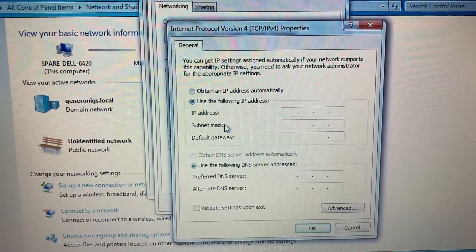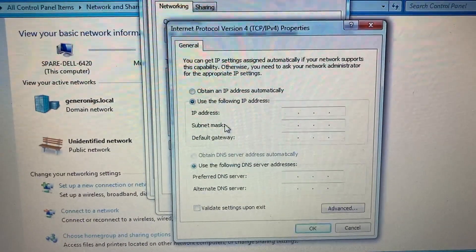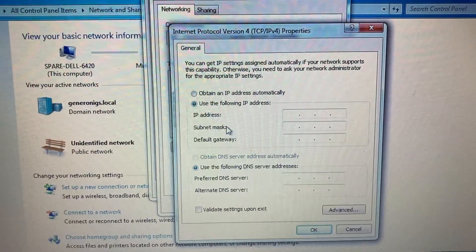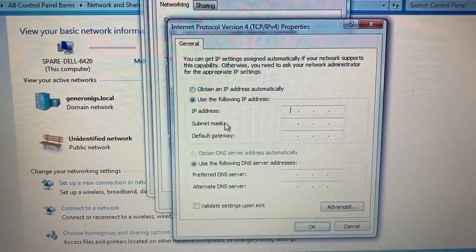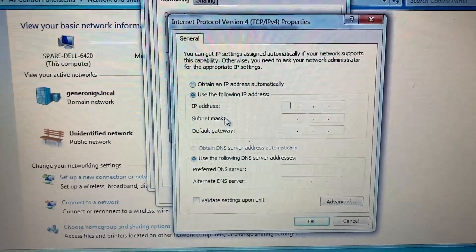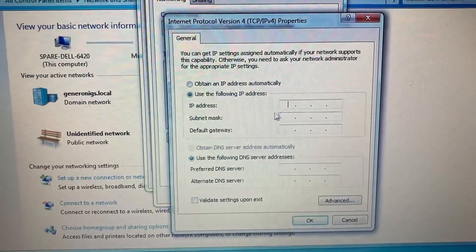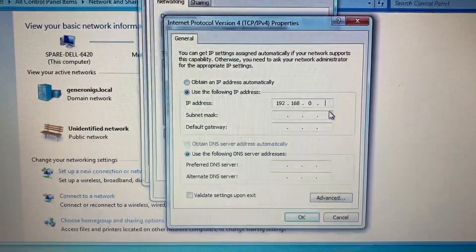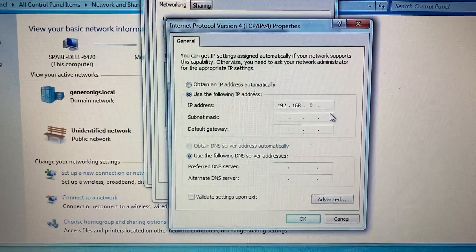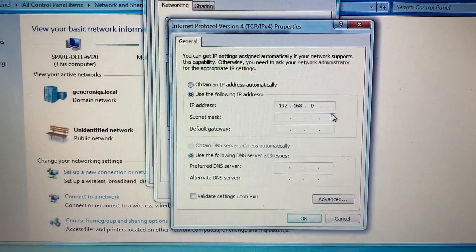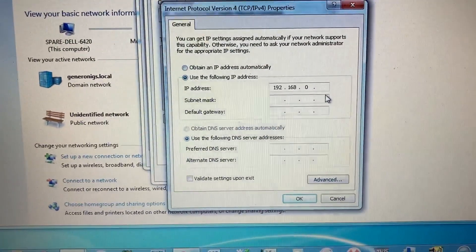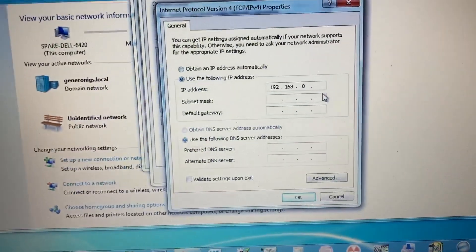The first three numbers of the computer IP address need to be exactly the same as the PLC. Only the last number is different from the PLC.